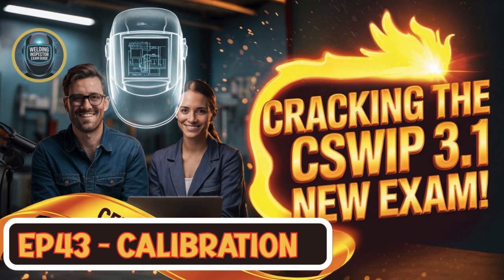Traceable. Okay, like a chain of accuracy. Exactly. It creates this unbroken chain, giving you confidence in the measurements. And yes, their accuracy is paramount. They should be at least 2 times, and ideally 5 times more accurate than the equipment they're actually checking. Wow, 5 times preferably. And for that precision grade welding equipment we talked about, you need instruments with even greater precision still. Okay, let's dive into the nuts and bolts of the actual measurements, because I hear some of these parameters have some real quirks that can trip you up.